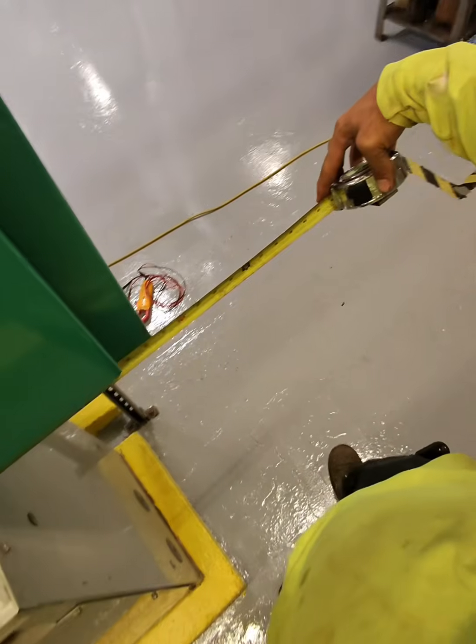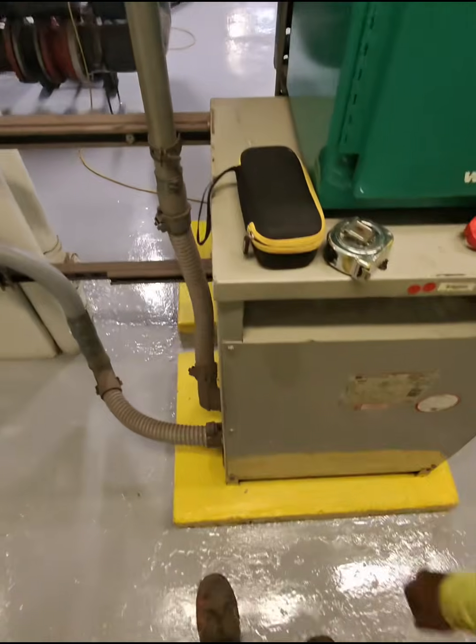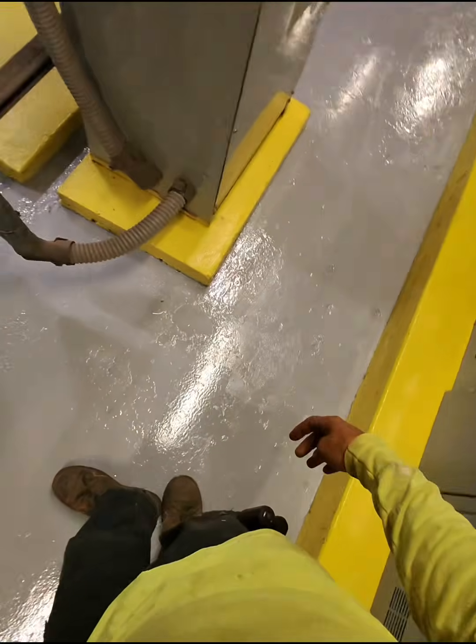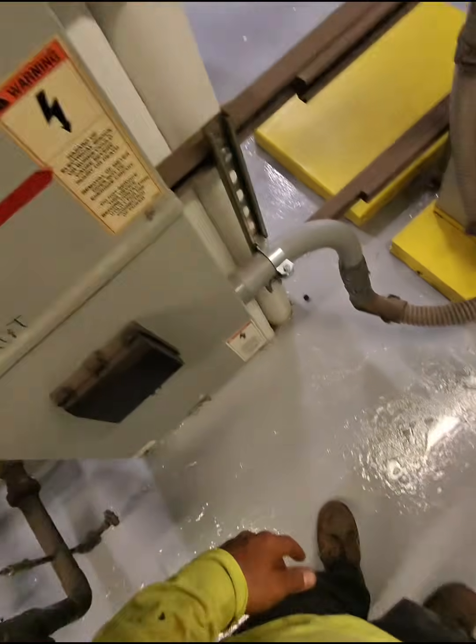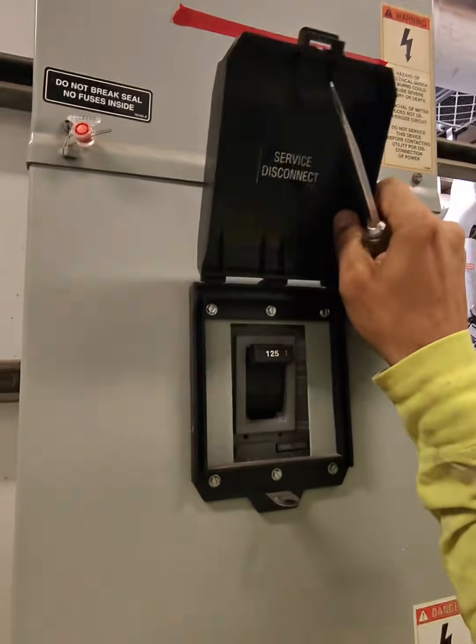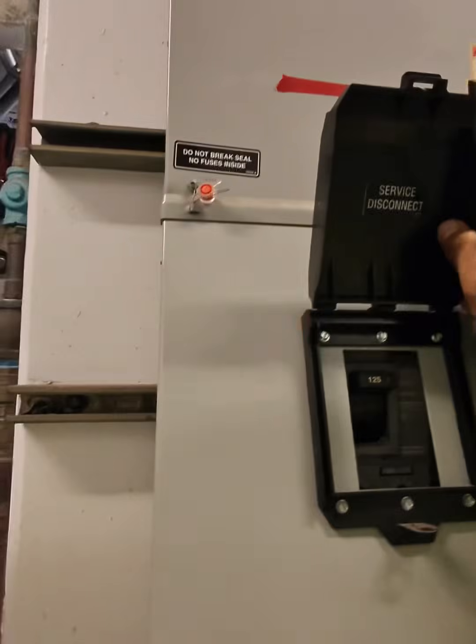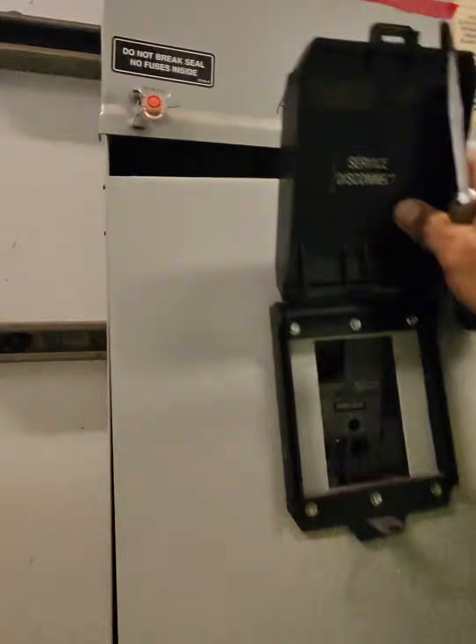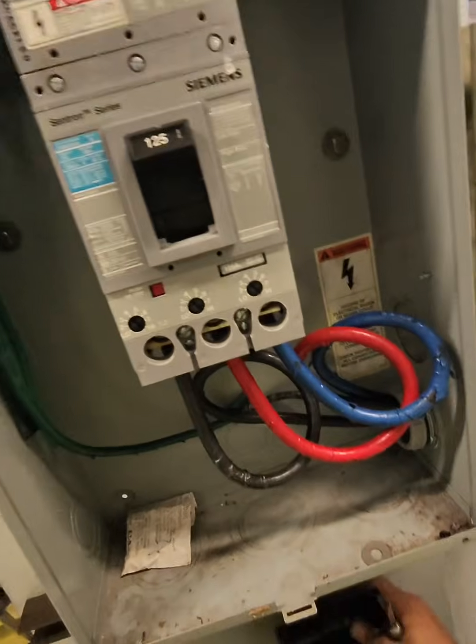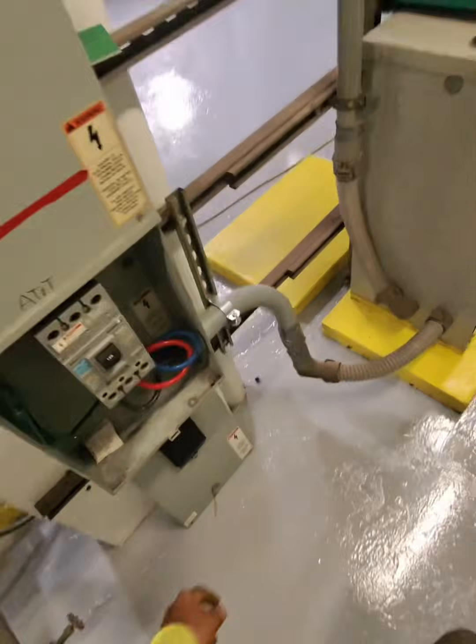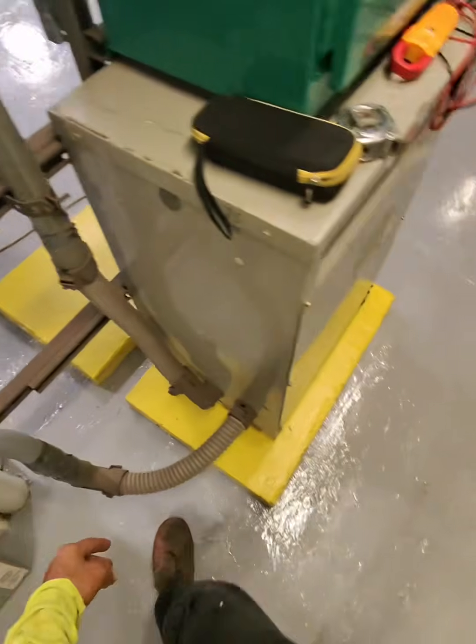15, 40, 30. I don't really want to open this up because it's live, but I do need to check the wire size. So I'm actually much more comfortable opening this side up to get my wire sizes. See right there, it says 1-aught. The last thing I need to do is find out where they got their GEC from and if we can reuse it.